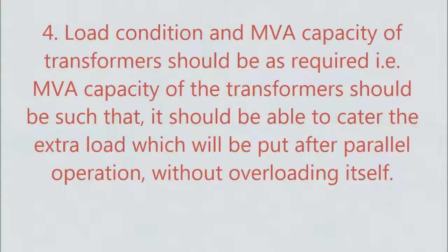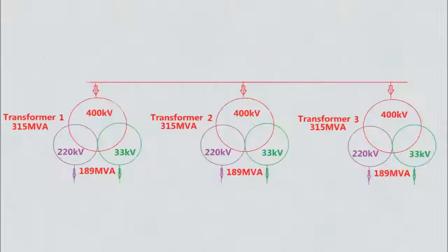The fourth condition is that the load condition and MVA capacity of the transformer should be as required — that is, the MVA capacity of the transformer should be such that it is able to cater to the extra load which will be put after parallel operation, without overloading itself.